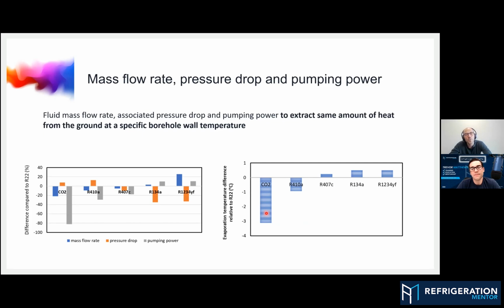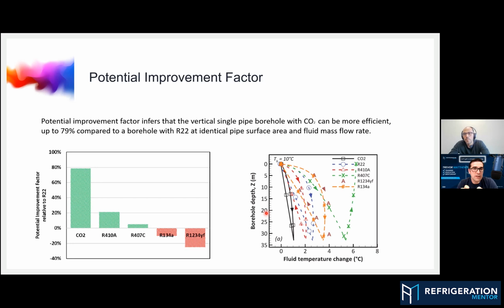And we wanted to find a way to overcome that problem and make that even more efficient than other refrigerants. Having to run that at a lower temperature with CO2, that's an issue because that means a higher compression ratio. Is that right? Because that's a -3. So we get a higher compression ratio, more work on the compressors, using more energy to get the same results. And just to be clear, that's because it's a smaller tube, less surface area to take in, right? Exactly.